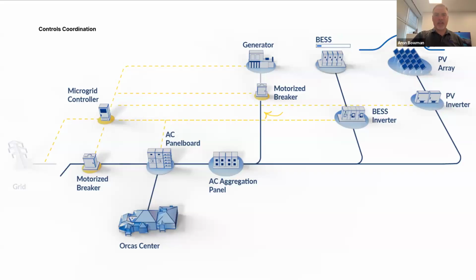Yeah, Markus, I can jump in here because this is where the microgrid controller that we've developed and been putting in the field comes in. We have over 300 active sites with microgrid controls with very similar setups to this, some grid tied, some completely islanded all the time. And to what Lucas was talking about, it's a constant monitoring of the entire system. When we talk about it, it's very straightforward. It's like, if this happens, we do this, but you're constantly monitoring that in milliseconds throughout the entire day. Like the grid outage, there are different types of grid outage.